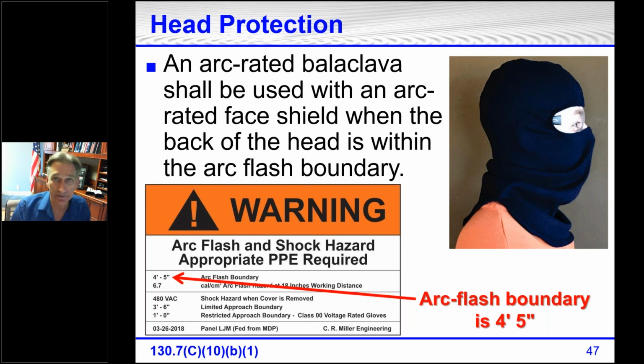I mentioned earlier that I've seen labels with boundaries as close as 3 inches, 6, 7, 8 inches, 1 foot, 12, 13 inches. If the back of your head is not within the arc flash boundary, you don't have to wear an arc-rated balaclava. If it is, yes, absolutely, you're required to wear the arc-rated balaclava.